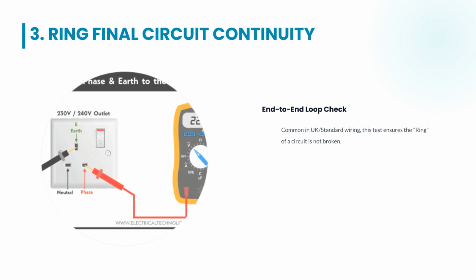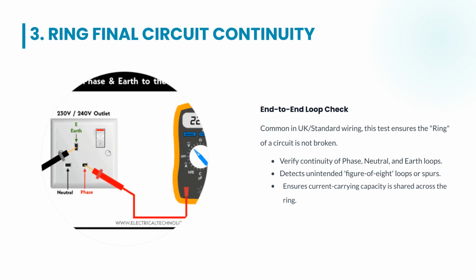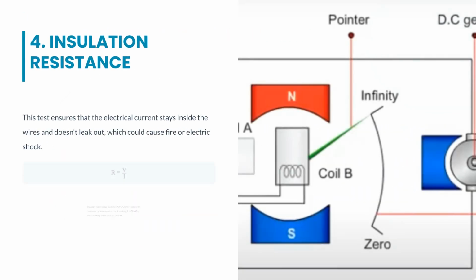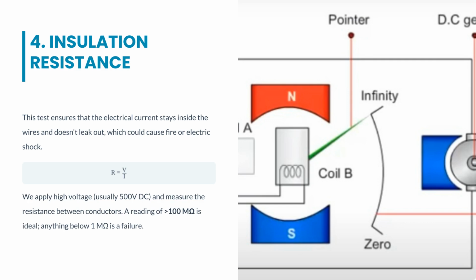Test number 3 is ring final circuit continuity, common in standard wiring. This end-to-end loop check verifies the continuity of phase, neutral, and earth loops, ensuring current capacity is shared and detecting breaks or spurs. The fourth test is insulation resistance. We apply high voltage, typically 500 volts DC, and measure the resistance between conductors. This confirms current stays within the wires, preventing fire or electric shock. A reading above 100 megaohms is ideal.